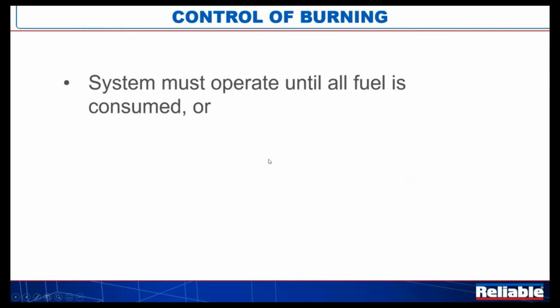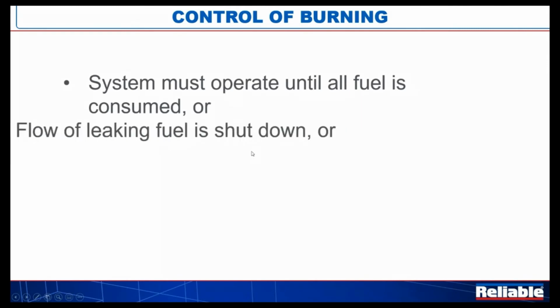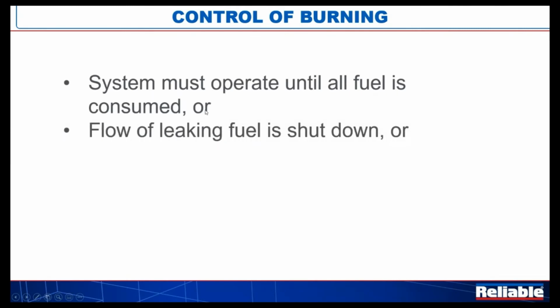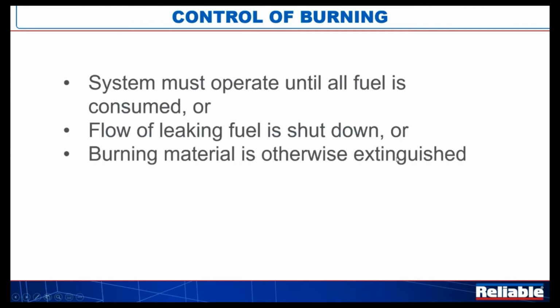What is that? I thought we were trying to do that everywhere. Well, you see as we get through the requirements here, what they're after is an open tank, like an oil quenching operation or a cleaning operation prior to painting, where you're dipping things down into liquid flammable materials and bringing them back up. So that's kind of what we're talking about here. So the system must operate until all fuel is consumed, or the flow of the leaking oil or whatever it is can be shut down, or the burning material is otherwise extinguished.